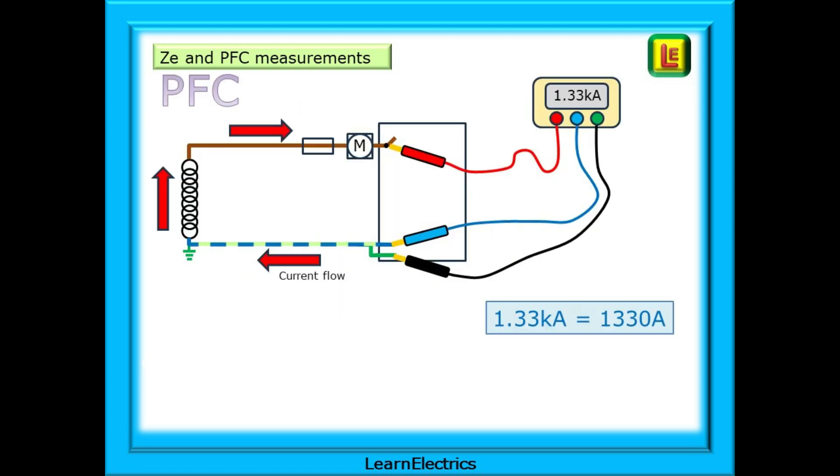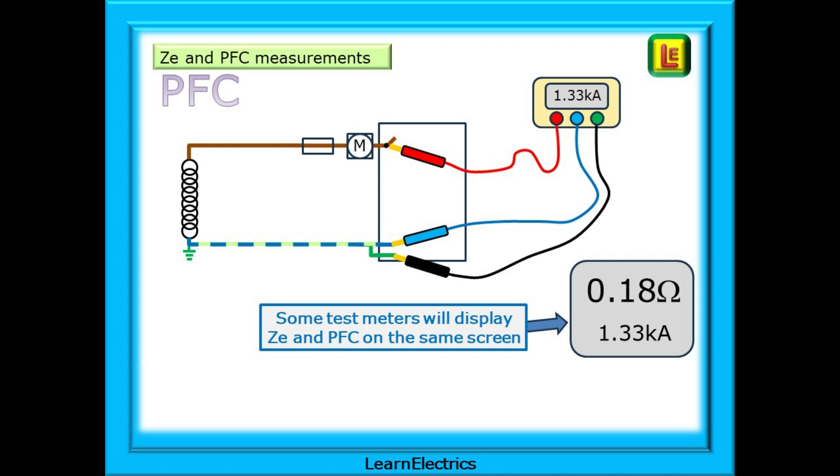So a three wire test on a TNCS system might return 1.33 kiloamps. Kilo - thousands of amps - and 1.33 kiloamps is the same as 1330 amps. Most meters will display results in kiloamps and again the test can be as a three wire test or a two wire test. Some meters will display ZE and PFC on the same screen as shown here. So one test will do the ZE and PFC at the same time. It's a useful feature but it's not essential.